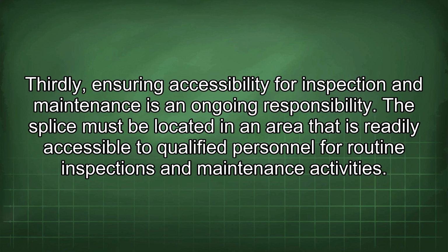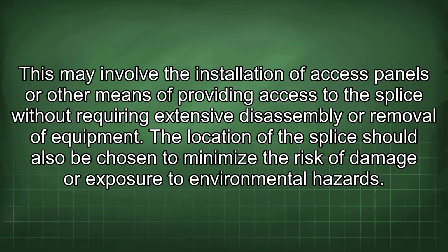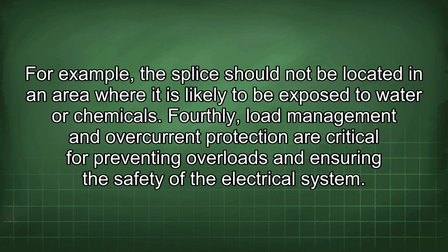Thirdly, ensuring accessibility for inspection and maintenance is an ongoing responsibility. The splice must be located in an area that is readily accessible to qualified personnel for routine inspections and maintenance activities. This may involve the installation of access panels or other means of providing access to the splice without requiring extensive disassembly or removal of equipment. The location of the splice should also be chosen to minimize the risk of damage or exposure to environmental hazards. For example, the splice should not be located in an area where it is likely to be exposed to water or chemicals.